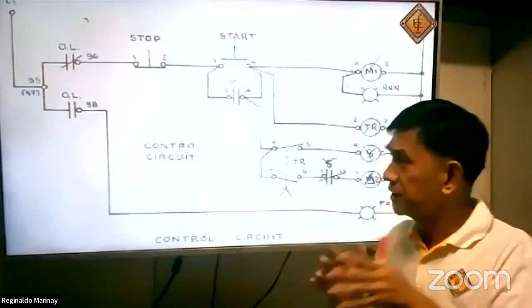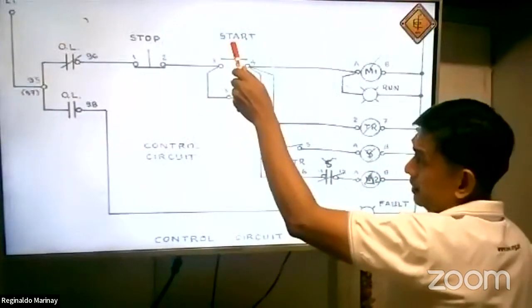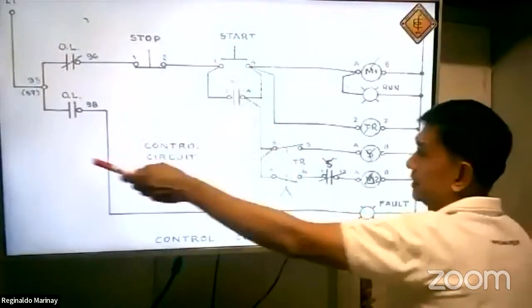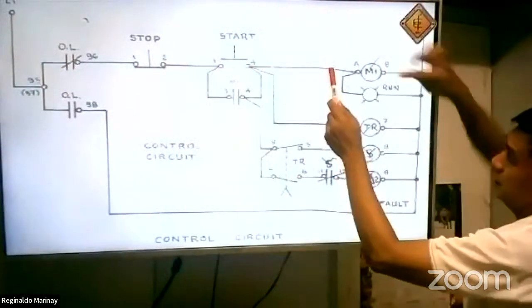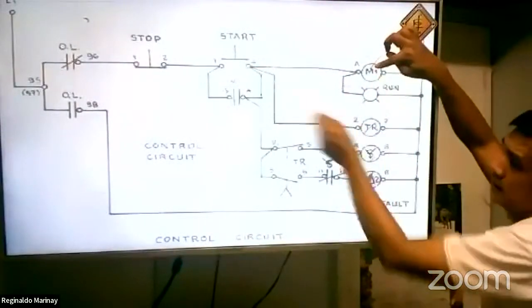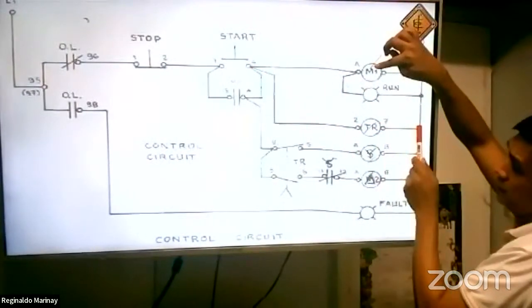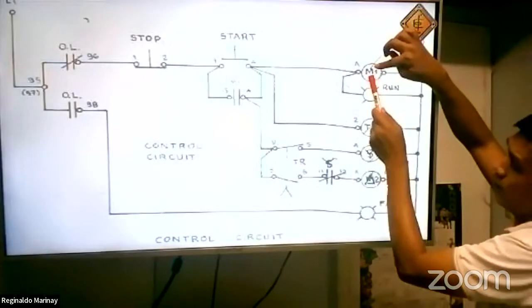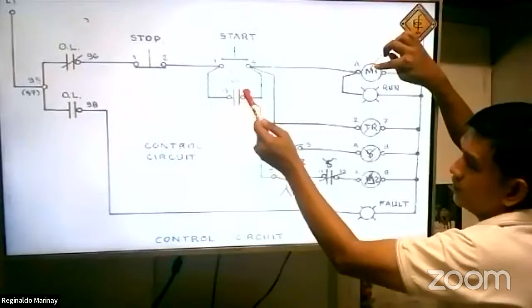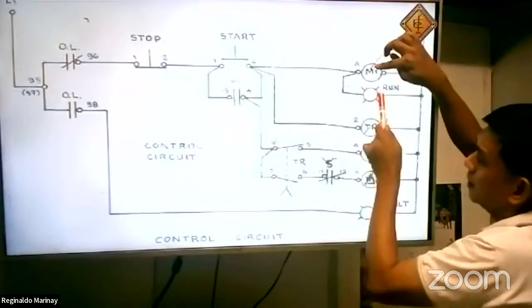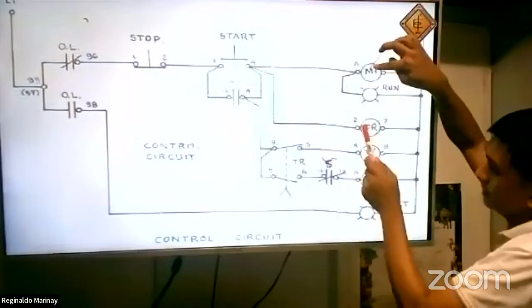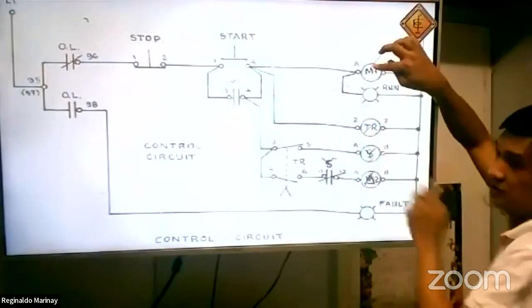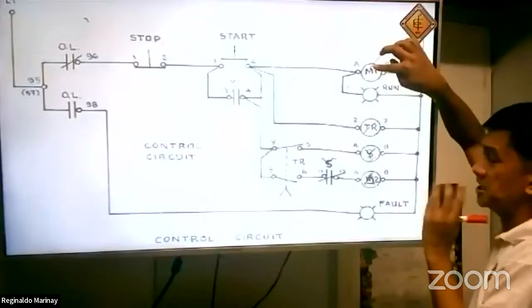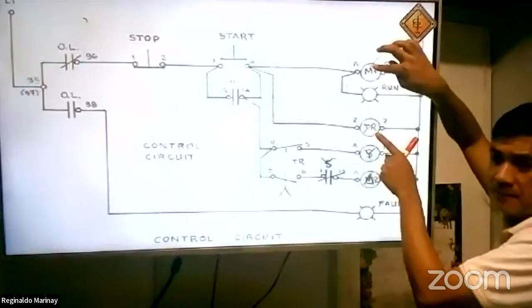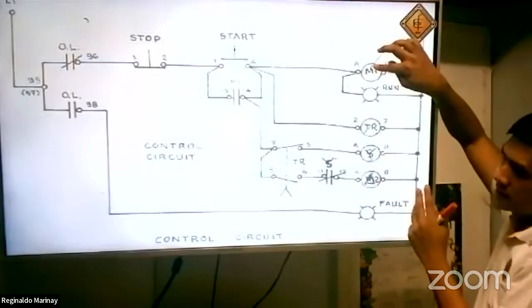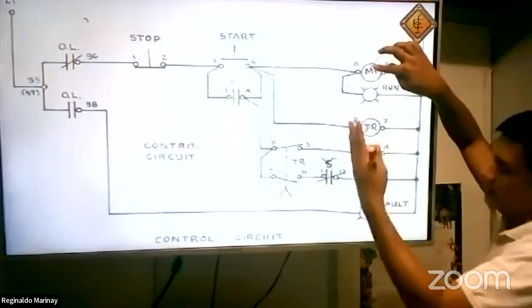What is the connection of the circuit? Once we close this circuit, we press this push button, and the current will flow from line 1, energizing your M1. Your run lamp is energized. Your timing relay will also be energized. Your M1 becomes energized, and your contact 1314 will become closed, right? The run lamp will light, of course. The timing relay starts counting once it is energized, from 0 to 2.99 seconds, 3 seconds, of course.